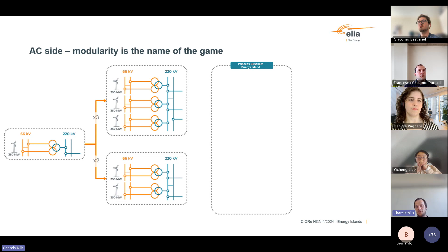And if we then look at how this looks in total on our island, we can see at the top we have twice this 1050 megawatt module connected to 3 AC 220 kV cables, bringing the 1050 megawatts in via AC to onshore. And then 2 modules with 700 megawatts of capacity connected to both of the poles of the HVDC bipole system, bringing the power onshore via the DC system, and also injecting it into the DC network so that it can basically go anywhere between Belgium, UK, Denmark. So this is the module design we have on the AC side.